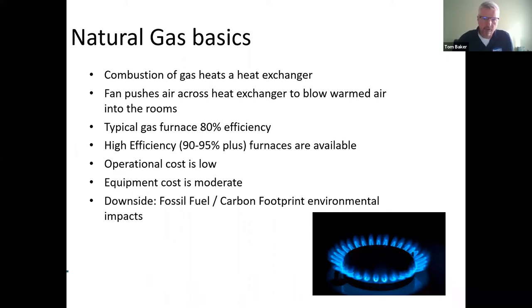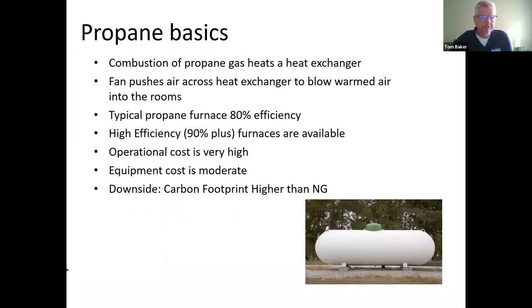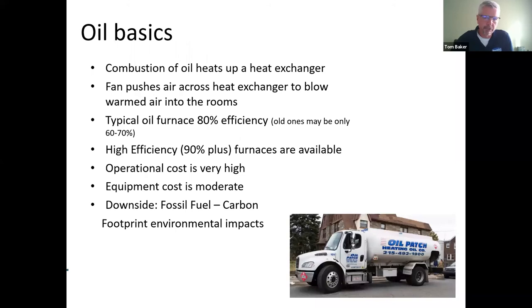If we go to propane next, it functions the same way by combusting fuel and running it through a heat exchanger. We get about the same efficiency, somewhere between 80 and 90% typically with propane, but propane's much more expensive per million BTUs, like we saw on our chart. So the operation cost is very high. Equipment cost is about the same. We'd consider it moderate. The downside, again, is that we're dealing with a carbon footprint that's even higher than natural gas.